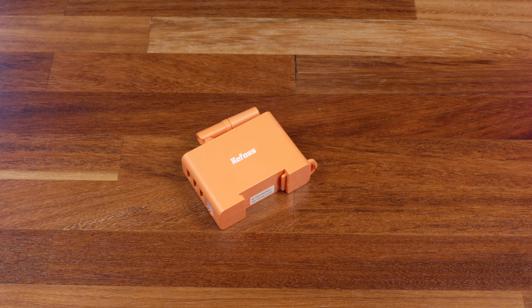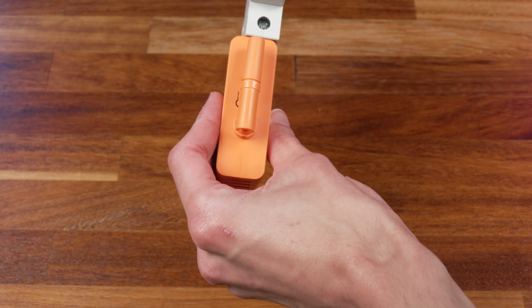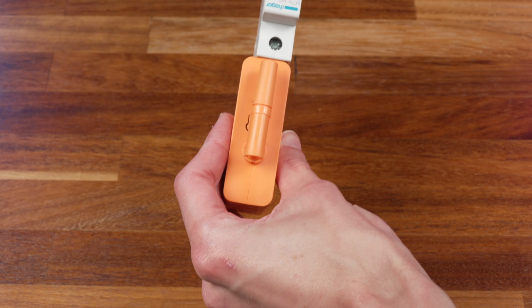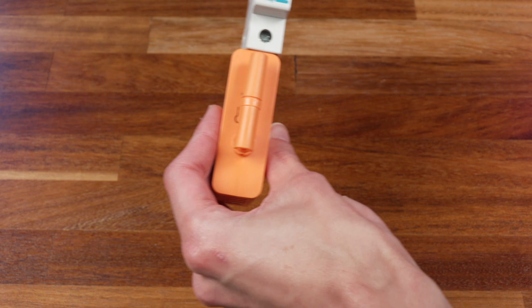So what that essentially means is that you're not meant to really mix combinations of devices into a consumer unit that the manufacturer hasn't tested. Or more specifically, you can do it, but you're essentially then taking on all the responsibility from the board onto yourself instead of the manufacturer. You can also maybe see here that it's also a fair bit wider than a standard DIN rail mounted circuit breaker, but not as wide as 2 of them.